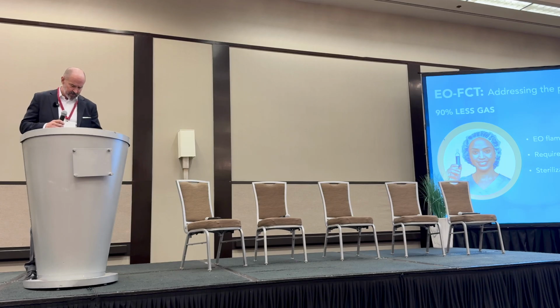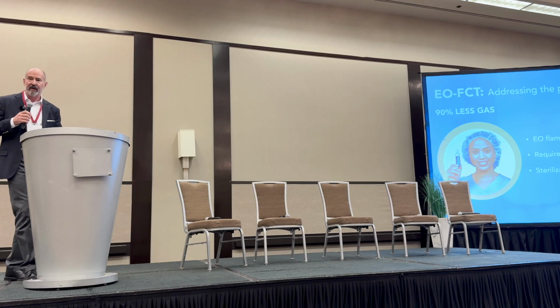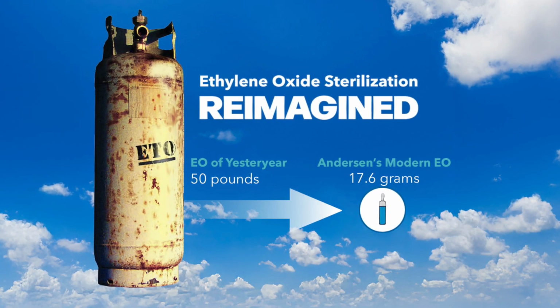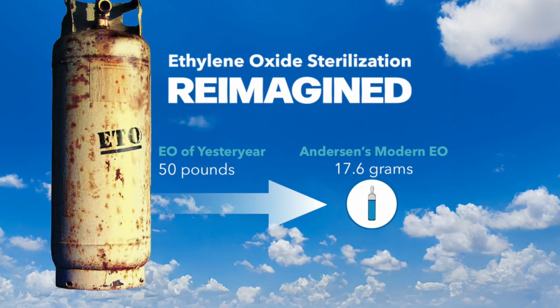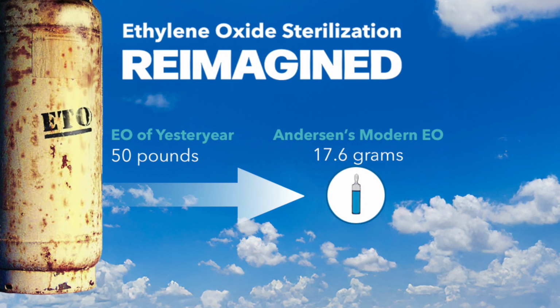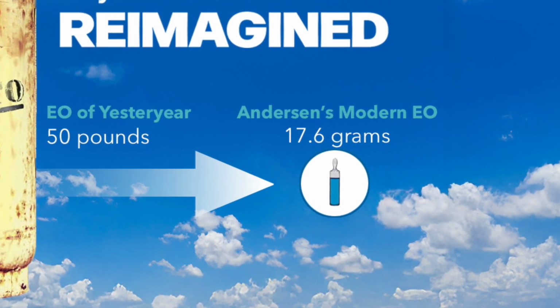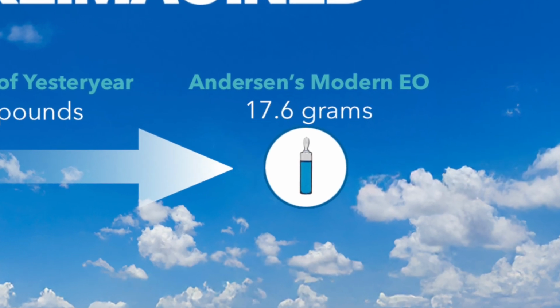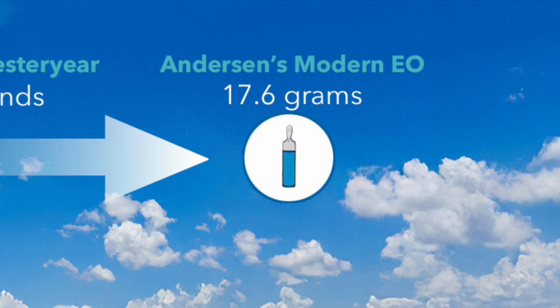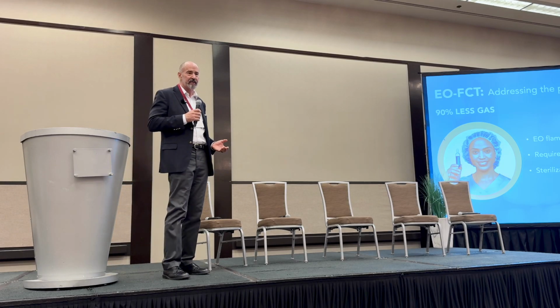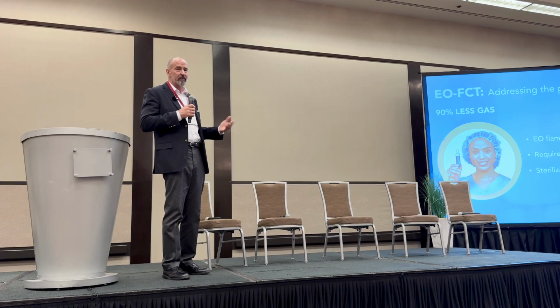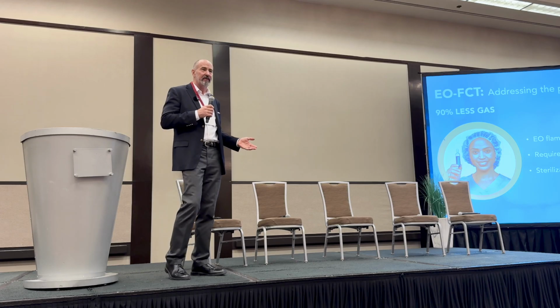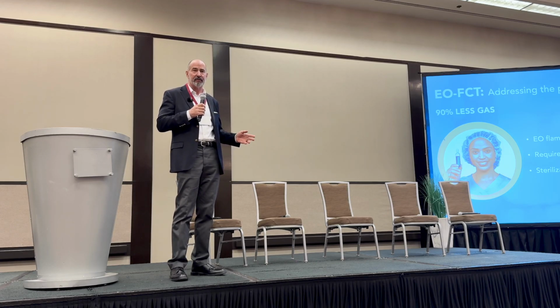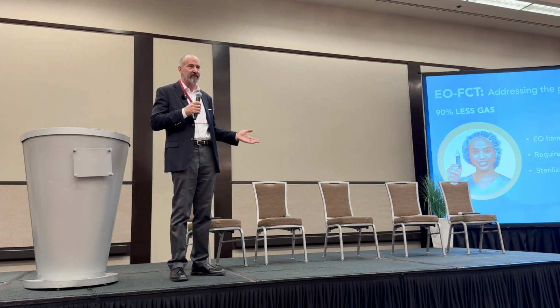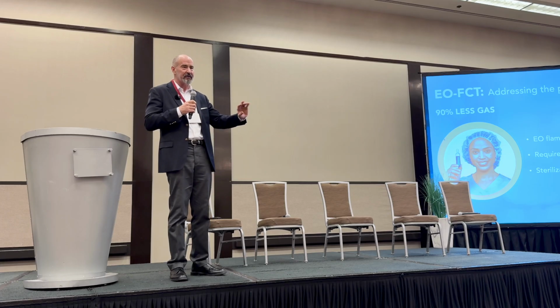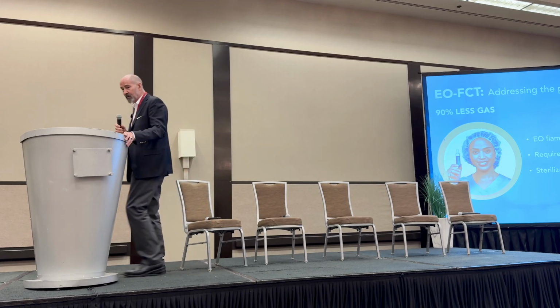As I said, the early methods of storing ethylene oxide, the tanks and the cartridges, all leaked. We are taking ethylene oxide and we are flame sealing it into glass ampules. Flame sealing ethylene oxide into glass is the only way that we've discovered to truly contain this amazing chemical. Because we're flame sealing the ethylene oxide in glass, you don't need ventilated storage. Again, we're using so little gas that we are completely exempted from all of the requirements of NFPA 55, which is the National Fire Protection Association's guidance on ethylene oxide. At the very start, it says, we don't care about systems that are using less than 200 grams of gas. We're using only 17.